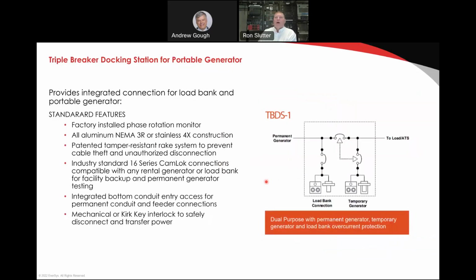They also have other pieces of equipment that you can purchase that are a little more advanced in their capability. You can see here on the right-hand side that this particular box is actually pre-configured like this and is bought with all of these features. So we have an interlock between the breakers. We have a temporary generator portable connection and a load bank portable connection so that you can facilitate utilization of CAM lock connectors to connect the portable generator or a temporary generator. What is a CAM lock connector? Well, if you've ever been to a carnival and you've seen those cables running on the ground and you can see the connectors on them.